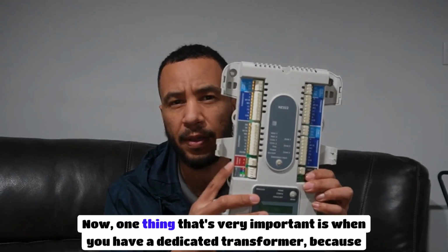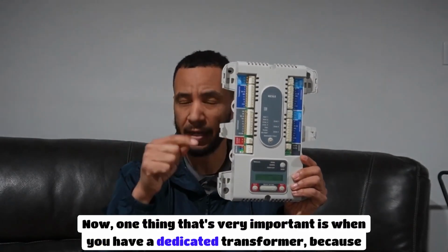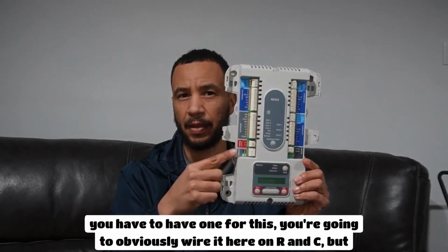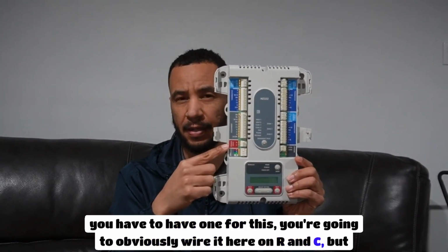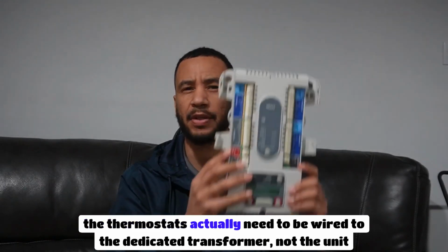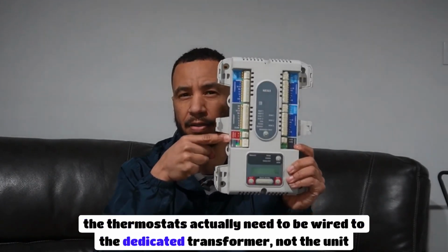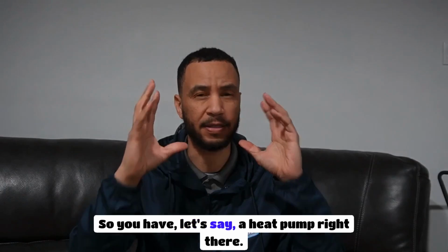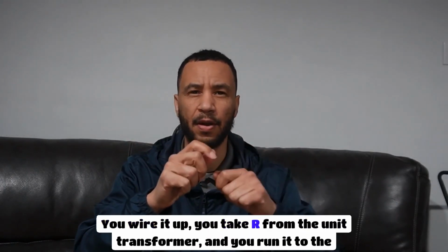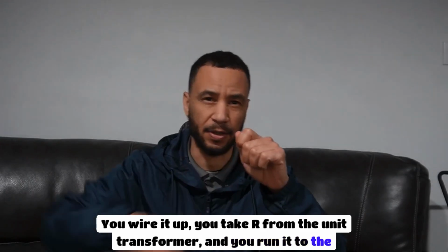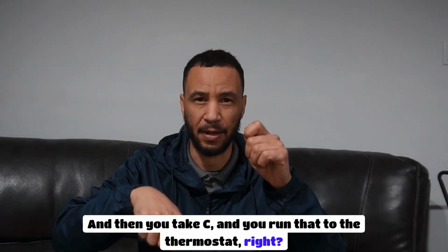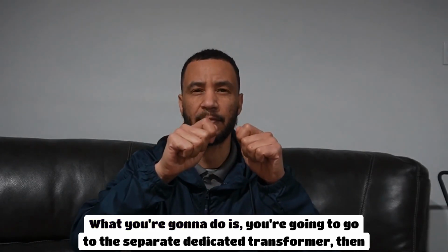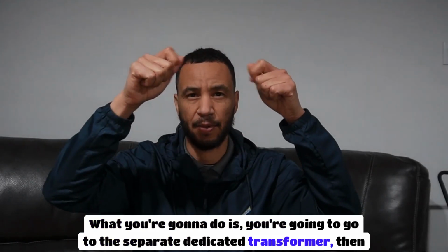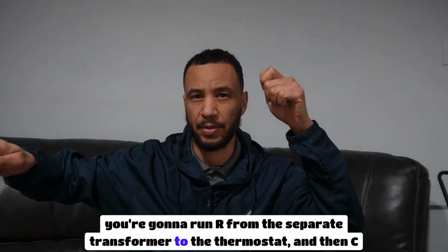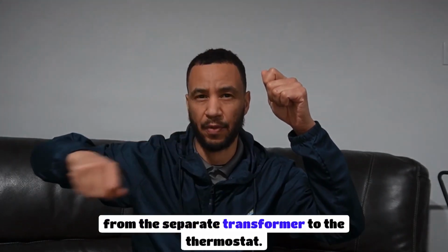Now, one thing that's very important is when you have a dedicated transformer, because you have to have one for this, you're going to obviously wire it here on R and C, but the thermostats actually need to be wired to the dedicated transformer, not the unit transformer. I'll say that again. So you have, let's say, a heat pump right there. You wire it up, you take R from the unit transformer, and you run it to the thermostat, right? And then you take C, and you run that to the thermostat, right? Not when you have a zone board. What you're going to do is go to the separate dedicated transformer, then run R from the separate transformer to the thermostat, and then C from the separate transformer to the thermostat.